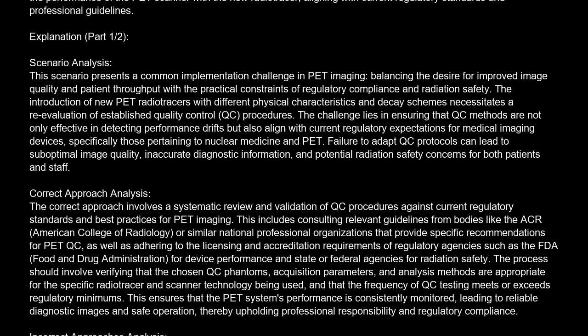Implementing a QC protocol solely based on vendor recommendations without independent verification against regulatory standards is also problematic. While vendor recommendations are valuable, they may not always encompass the full scope of regulatory requirements or address specific clinical needs and local operating conditions.